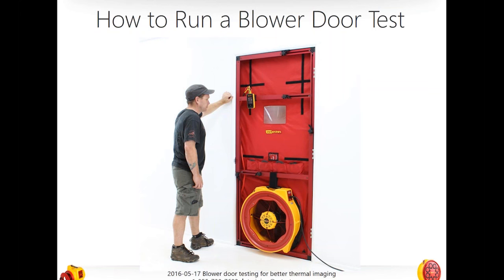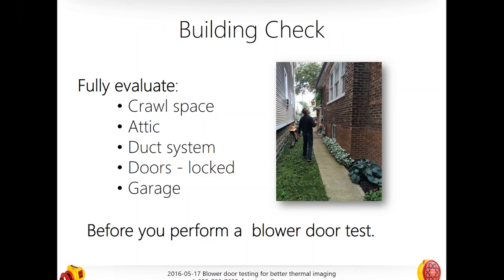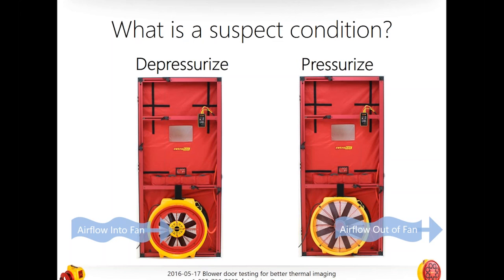You can feel cold air in a room with leakage, but you don't know where it's coming from. Let's talk about how to run a blower door test. If you are running a blower door in conjunction with thermographic imaging, first do a building check. It is critically important that you do a full evaluation — not just for health and safety, but if you're doing a thermographic check and you don't understand what's inside and outside, where the thermal boundary is, and how the house is framed, you'll have a very difficult time interpreting your thermographic images.